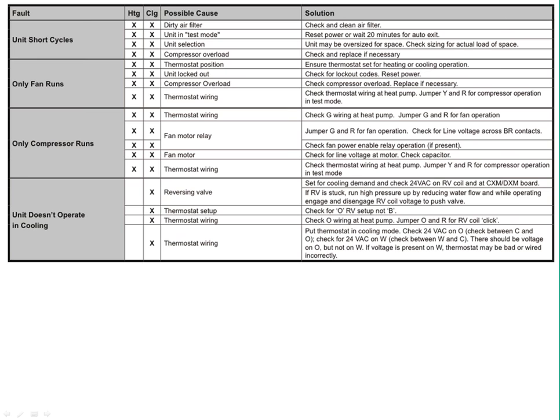Again, guys, back on the following page in that CXM IOM section, you're going to see some other areas that I bet a lot of you didn't know were available to you. For example, on the left, here's some of those issues. Unit short cycles, or only the fan runs, only the compressor runs, or the unit doesn't operate in cooling. So again, whether you're in the heating or cooling mode, you see that checkbox, possible cause with the solutions over to the right.